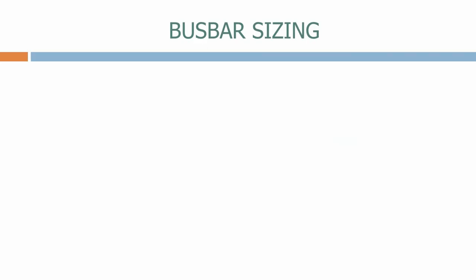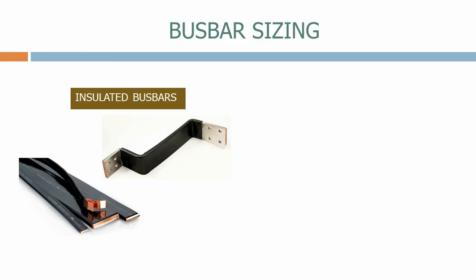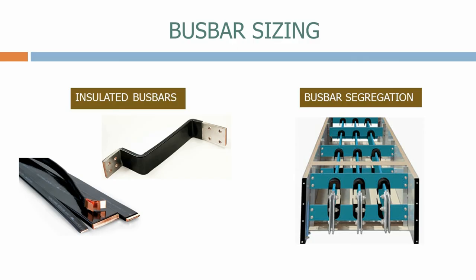We obviously want to minimise the chance of a fault occurring, and switchgear manufacturers use many methods to achieve this. These include using insulated busbars, where we coat a copper or aluminium conductor in a plastic coating, which minimises the chance of the busbar arcing across to the grounded housing. The other technique is busbar segregation, where the red, yellow and blue busbars are all housed in separate grounded channels, minimising the chance of a phase-to-phase fault occurring.